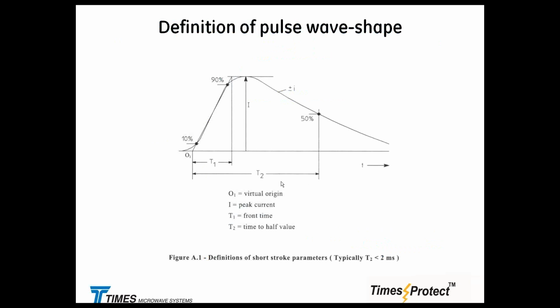So how does the current look? We know that it's going to be short in duration, anywhere from 20 to 30 microseconds. If you take a look at the lightning current signature, you are going to have a couple of values. There will be the rate of rise time, how quickly that current is going to go from zero, to simplify everything. We are marking that at 10% because we are allowing in this case for that 10% to be step potential rise where the current doesn't flow yet to 90. So the actual rate of rise time is measured from 10% up to 90% of the current wave shape.